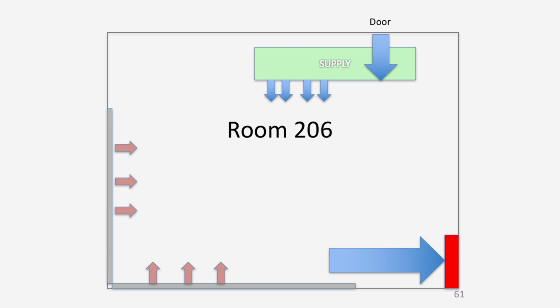Room 206 housed a child with severe combined immune deficiency. For whatever reason, that hospital put that child in that room under negative pressure. And what we see essentially is that with that, and you probably can't see that, most of you are looking at a piece of paper, that the supply air was less than the exhaust. In addition, when the door opened up, that was even less than the total exhaust. And what ended up happening was that air came in around the mullions on the windows.